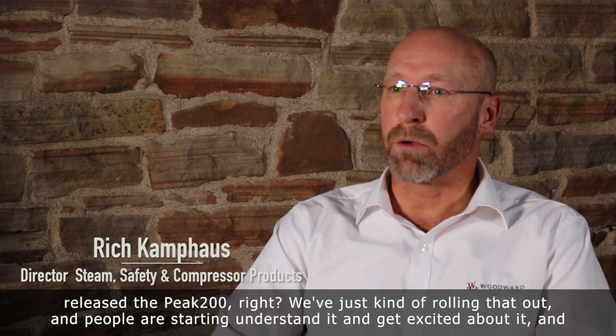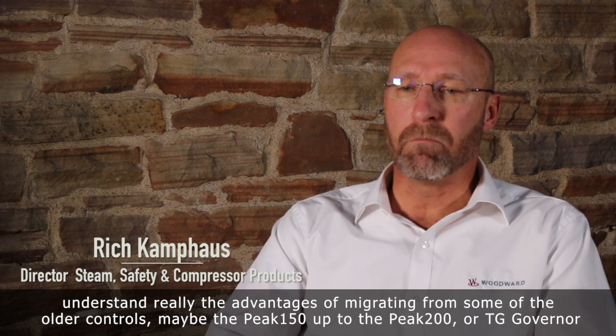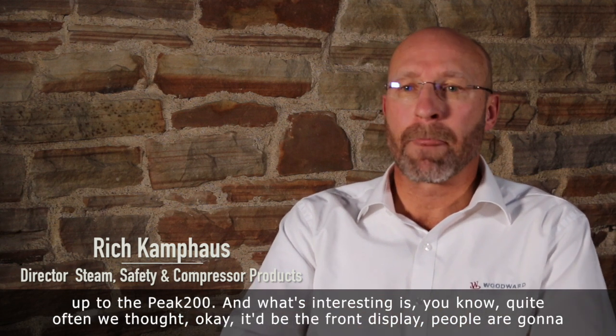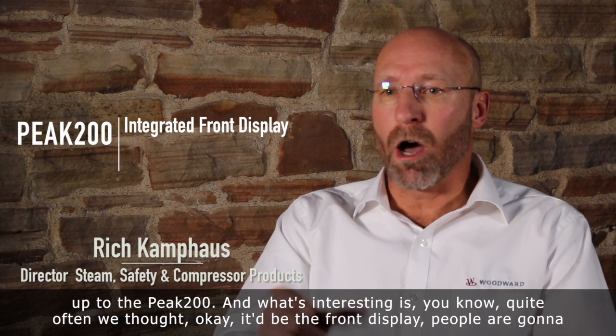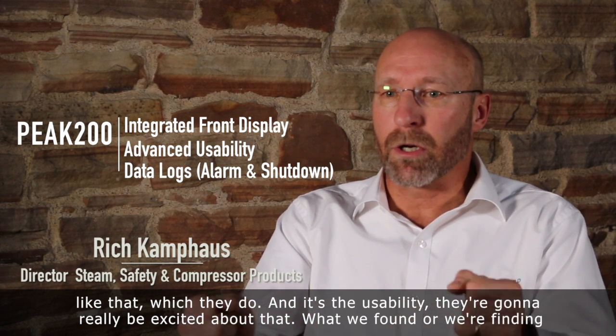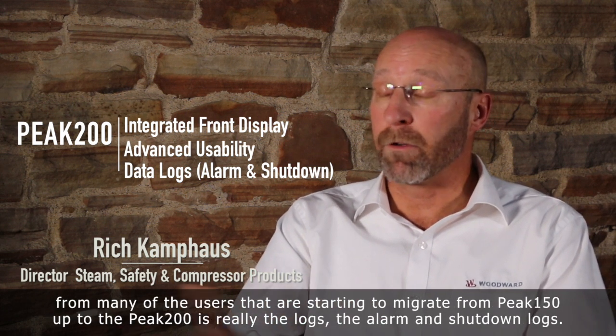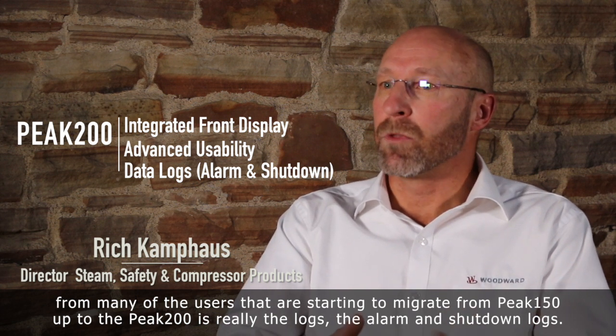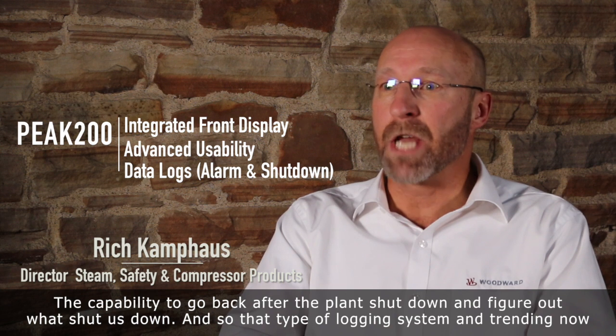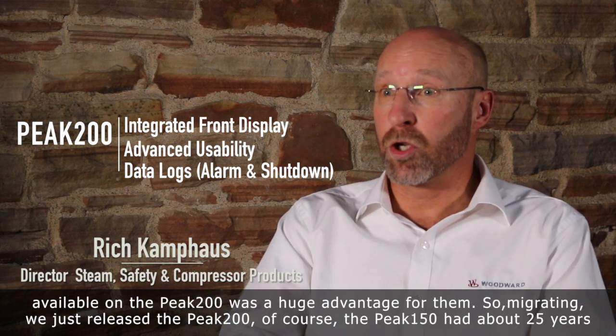We just released the Peak 200 and are rolling it out. People are starting to understand it, get excited about it, and understand the advantages of migrating from some of the older controls — maybe the Peak 150 up to the Peak 200, or a TG Governor up to the Peak 200. What's interesting is we thought the front display and usability would excite people, which they do. But what we're finding from many users starting to migrate from Peak 150 to Peak 200 is really the logs — the alarm and shutdown logs. The capability to go back after the plant shut down and figure out what shut it down. That logging system and trending available on the Peak 200 was a huge advantage for them.